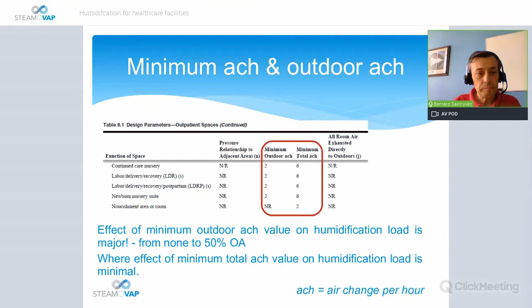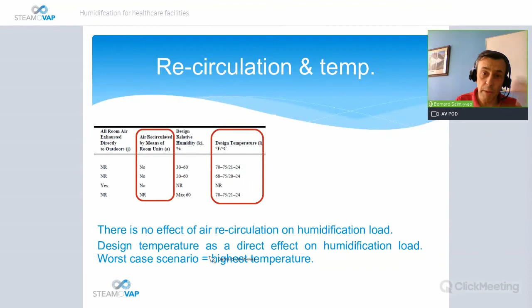All right. So then the next parameter is the recirculation and the temperature. The air recirculation will have no effect on the humidification load, obviously, but the design temperature will have a direct effect on humidification load, because the worst case scenario will be the highest temperature. If you have very high temperature with the same relative humidity, you will need more addition of water to the space. So a good practice for the engineer would be to calculate the humidification load for the highest temperature that is indicated, not the lowest, or we might lack humidity.